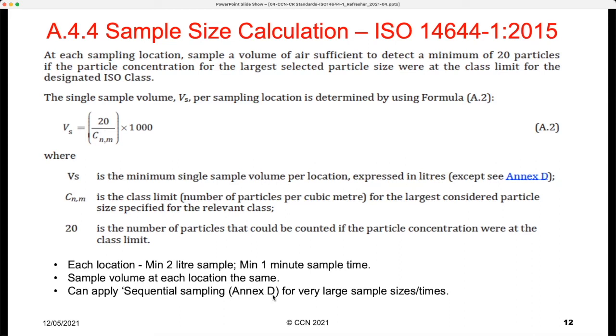Sequential sampling, covered in an informative annex, is a mechanism for very large required sample sizes. By monitoring the rate of count acquisition you can predict whether you will easily comply or exceed the class limit, allowing you to either shorten your sampling or abandon the test if it looks like you will fail — a useful tool for managing very large sample volumes and times.